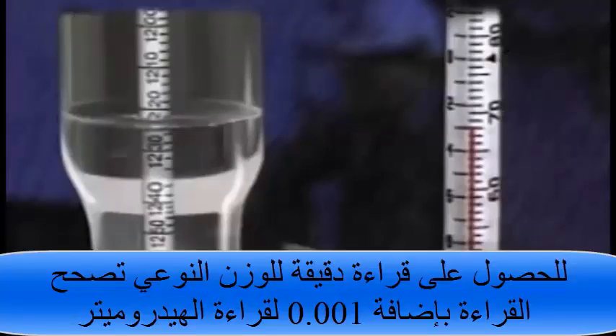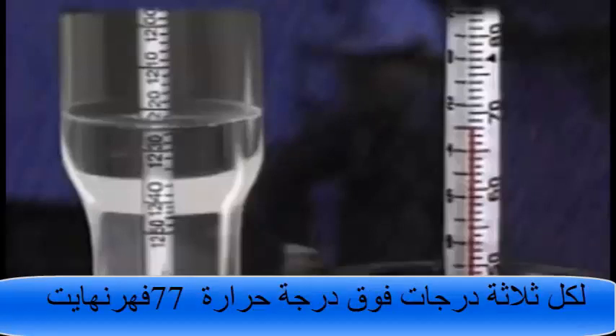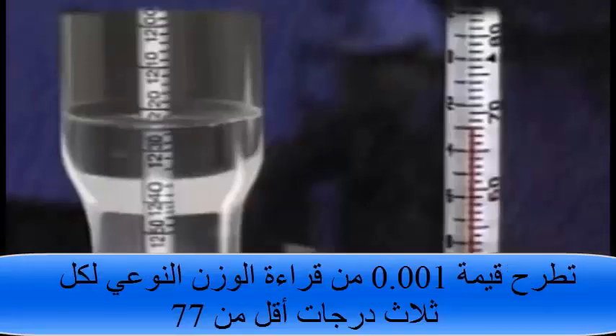To get an accurate specific gravity reading, the specific gravity is corrected by adding 0.001 to the hydrometer reading for every 3 degrees above 77 degrees Fahrenheit. For every 3 degrees below 77 degrees Fahrenheit, 0.001 is subtracted from the specific gravity reading.